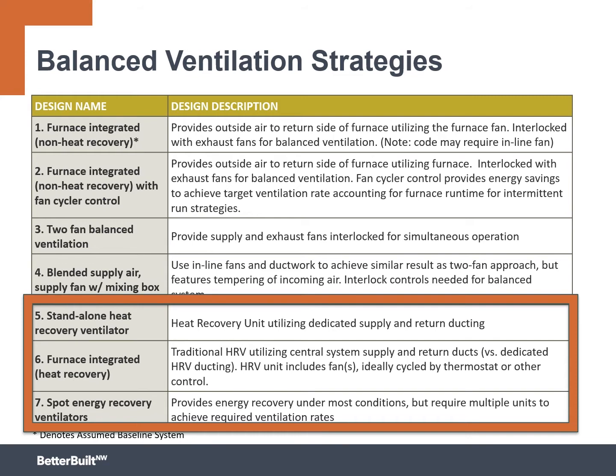And so this can actually have a little bit of energy savings, and potentially comfort benefit, because you're not always constantly blowing in untempered outdoor air. We can talk about using 2 fans, an exhaust fan somewhere and a separate supply fan, which is fairly easy to get balanced, but now you're not tempering that outdoor air at all. We could use a blended supply air box. So we actually attach a mixing box to our supply air fan and make sure that we pull some air from inside the house, some air from outside of the house, and then exhaust the same amount that we were bringing in from outside.